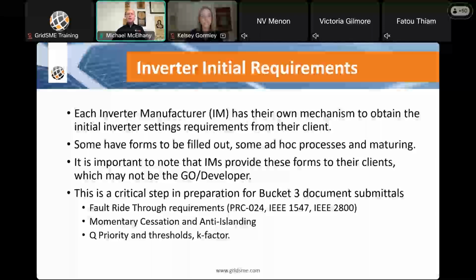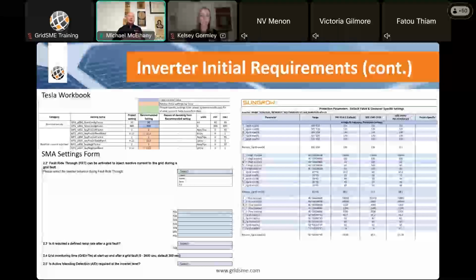How that particular inverter is set up to disable momentary cessation and anti-islanding is very different from inverter manufacturer to inverter manufacturer. And then Q priority, reactive capability priority and thresholds, and then the K factor, which we'll go into in a lot more detail. So my goal is always to help clients achieve a one and done getting through CAISO when you get to bucket 3. I'll let you know if we ever achieve that, because there's always some little nuance, but we try to get it as close as possible so that the turnaround, once CAISO provides comments back, is quick, as soon as we get those, we're addressing them. Our goal is to save time on the bucket 3 reviews and the attachment A reviews so that we can get through the process quickly.